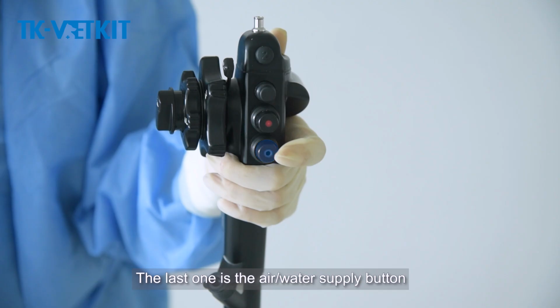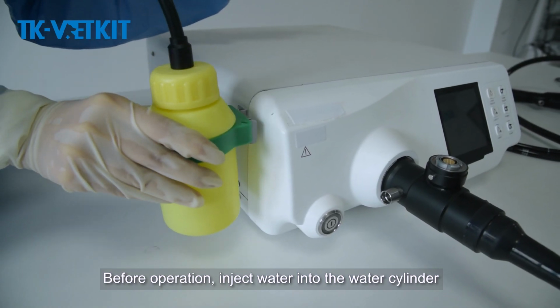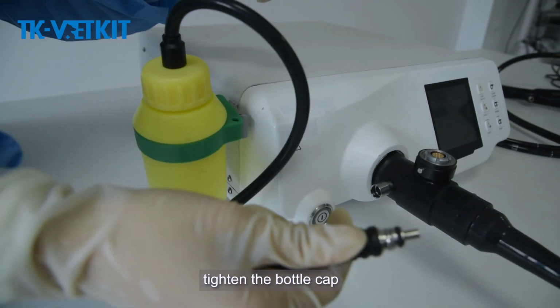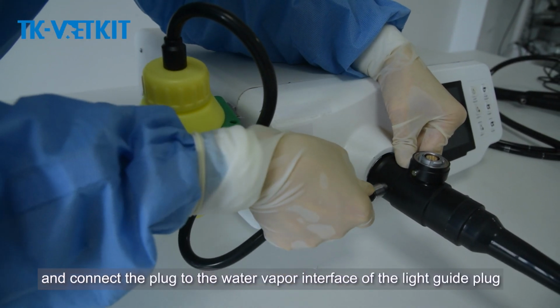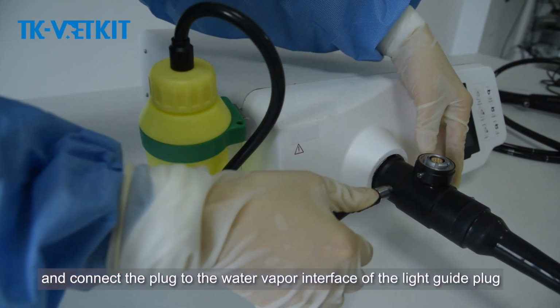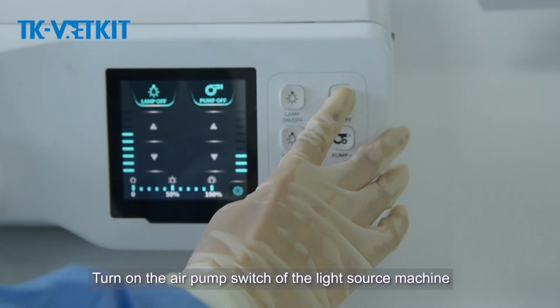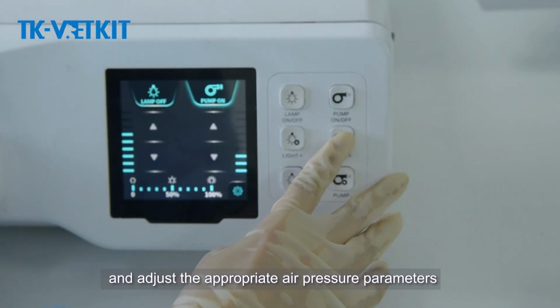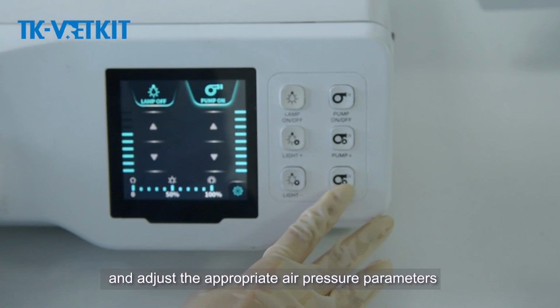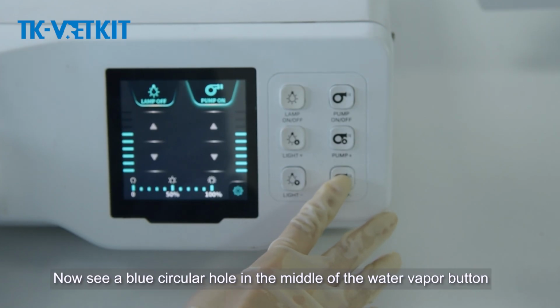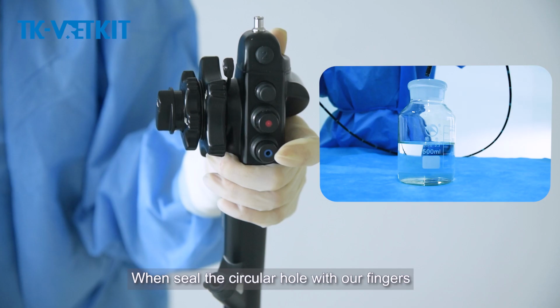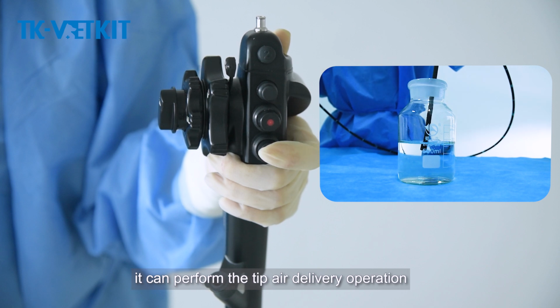The last one is the air/water supply button. Before operation, inject water into the water cylinder, tighten the bottle cap, and connect the plug to the water vapor interface of the light guide plug. Turn on the air pump switch of the light source machine and adjust the appropriate air pressure parameters. Now see a blue circular hole in the middle of the water vapor button. When you seal the circular hole with your fingers, it can perform the tip air delivery operation.